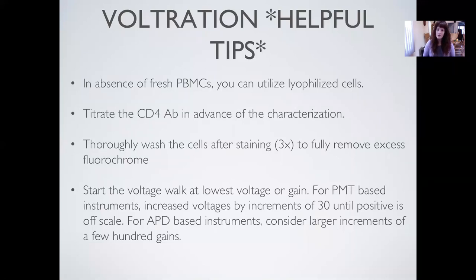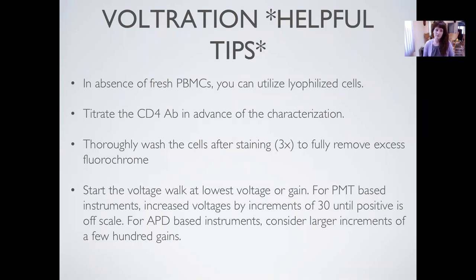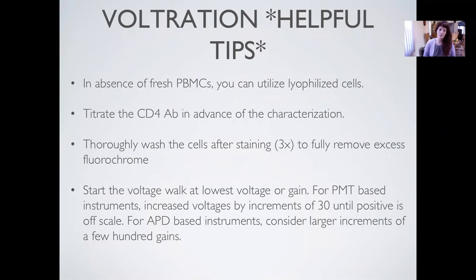Because you're likely using CD4s conjugated to polymer-based dyes, best practice is to thoroughly wash your cells after staining to remove excess fluorochrome — three washes after staining should be sufficient. This approach today is geared towards PMT or photomultiplier tube-based instruments. We suggest starting at the lowest possible voltage, around 200, and doing incremental increases of 30 volts at a time until we see the positive signal go off scale.